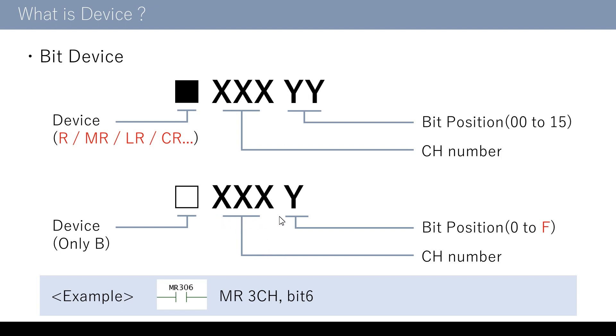For the device called B, which is used for Ethernet IP communications, all device numbers are displayed in hex from 0 to F. Therefore, the last digit becomes 0 to F indicating the bit position, and other digits indicate the channel number. For example, MR306 indicates bit 6 of the third channel in the device called MR — it does not mean the 306th bit of MR.